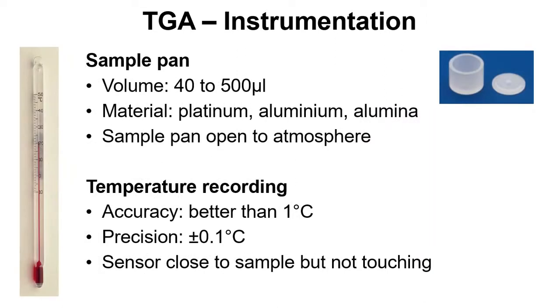The sample pan volume typically is between 40 to 500 microliters. We can use different materials like platinum, aluminum, or alumina, and the sample pan is open to the atmosphere to allow any gases to escape that are being evolved from our solid material.